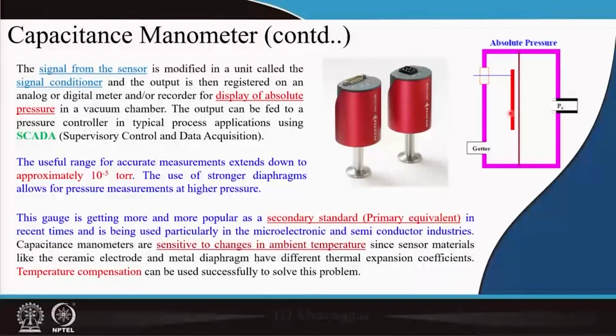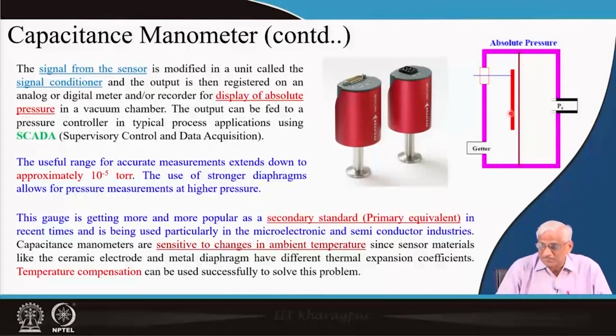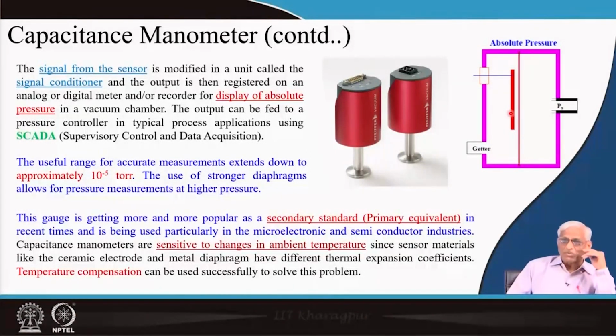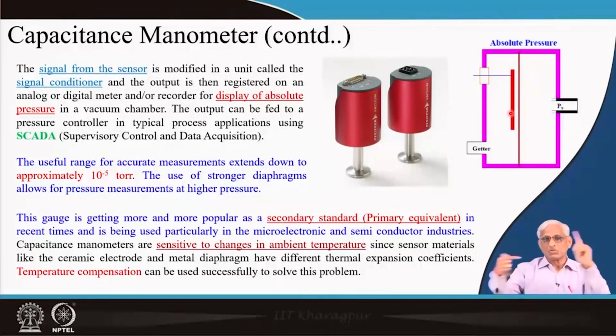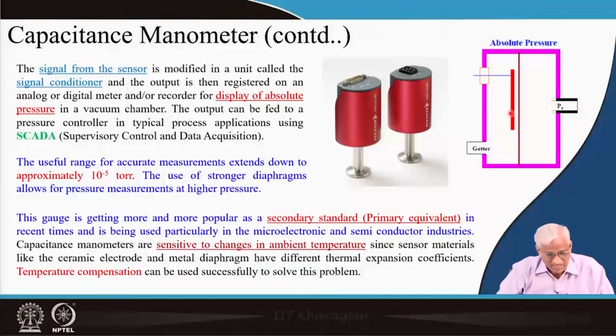With accurate experiments, this gauge can measure roughly up to 10 power minus 4 to minus 5 torr. It can be used to calibrate other gauges like Pirani gauge, by connecting two gauges with a T-arm to a chamber, with a needle valve and a pump. By compensating the inlet of some gas and exhaust by the pump, you can stabilize conditions. Whether it is stable or not, the gauge will show it on an electronic display, and it can be calibrated with a McLeod gauge. We will see this calibration procedure in the next class.